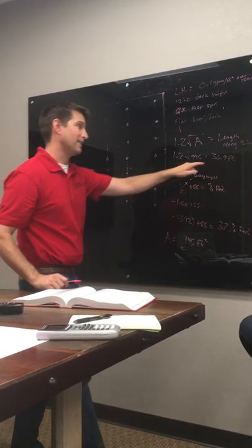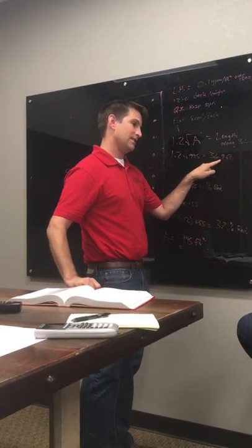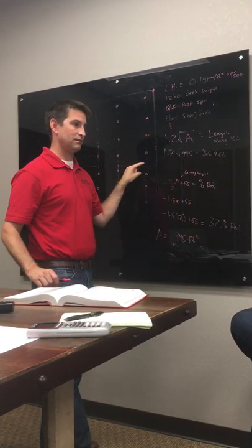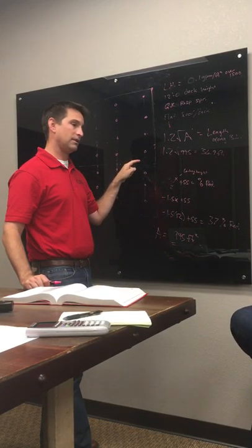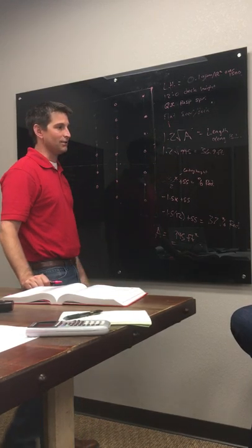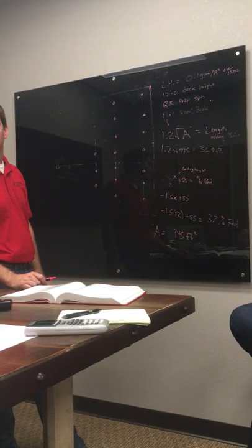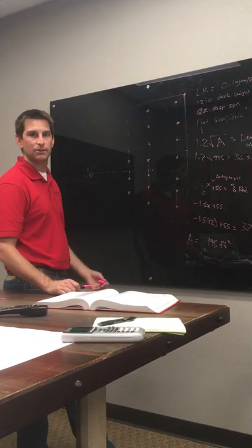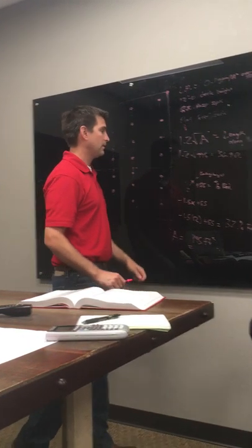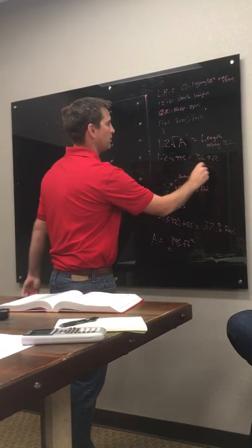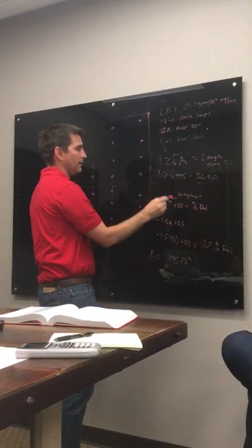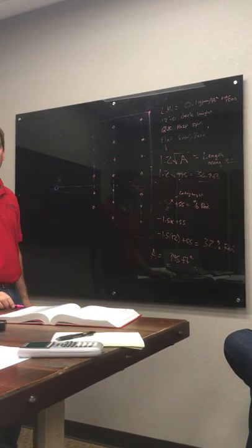If it falls under the halfway point, 36.9, where 37 is over, don't go over. Go to that 36.9. Don't go further than you have to. The codes are written with a safety factor, so don't do more than you have to. So we put that in, we draw our 30, we get our 9. Then we have to make sure we get at least 945. That's it. Pretty easy.